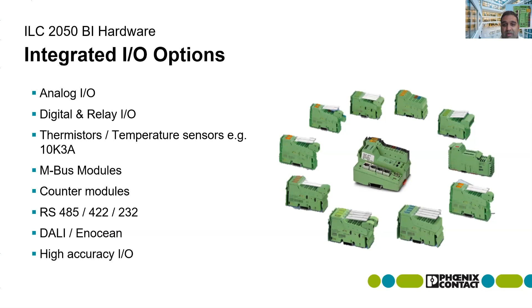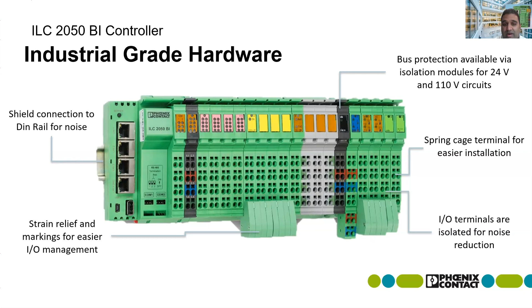As I said earlier, because it's an industrial grade product, you get a lot of the benefits of the industrial market, things like the shield connection for DIN-rail to minimize noise. You've also got isolated terminals for further noise reduction. A lot of the controls, and you can see the channels on these output modules, are spring cage, so from an engineering perspective the rollout of these controls is much quicker and more efficient. Even simply by changing a module, you can take the top header off the block, slide out the module, and reinsert a replacement module. There's also the bus protection that's available to isolate different voltage circuits within your design. So the entire flexibility of the hardware, with the complement of the software that Niagara provides, is really quite cool. We also have a central I/O solution.